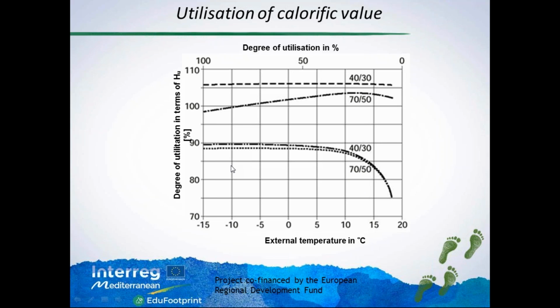And if we operate the boiler at a lower temperature stage, 40, 30, for example, to feed some radiation panels, the efficiency of a normal boiler is not that different. It's a little bit different if the outer temperatures are really very cold, but by 0.5 degrees, the difference is just 1-2 points of efficiency.